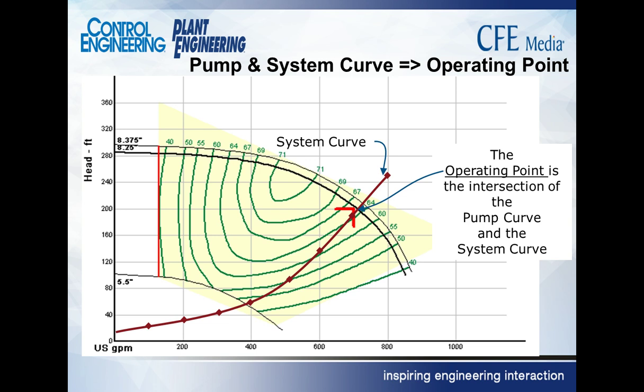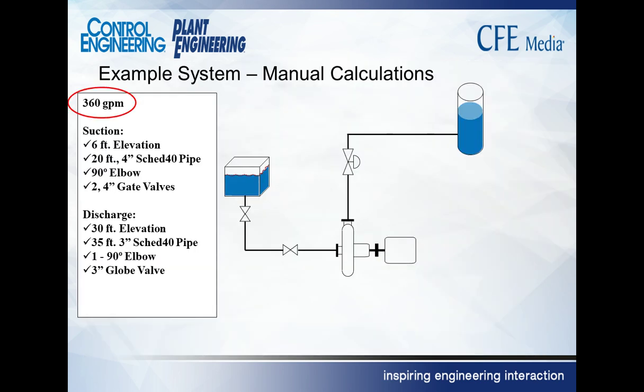The system is the combination of pipes, valves, heat exchangers, anything through which the liquid flows other than the pump itself. The operating point is going to occur at the intersection between the system curve and the pump curve. The intersection between the system curve and the pump curve will be the operating point. So let's take a look at what goes into developing a system curve so you'll have a good idea of what that is. Here's a typical system.